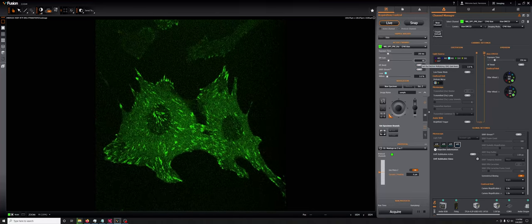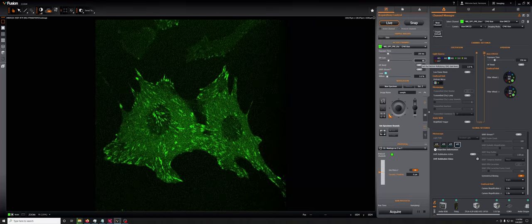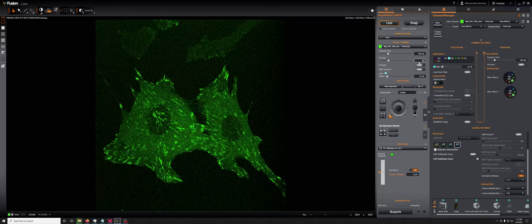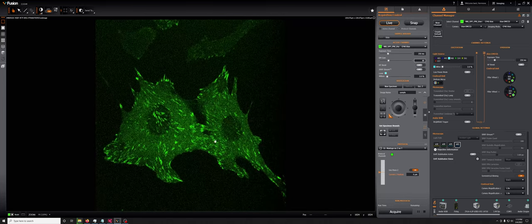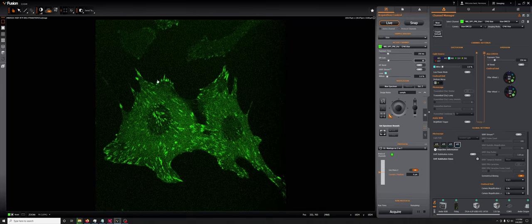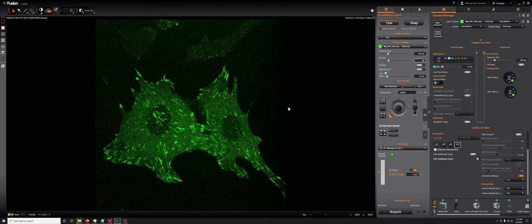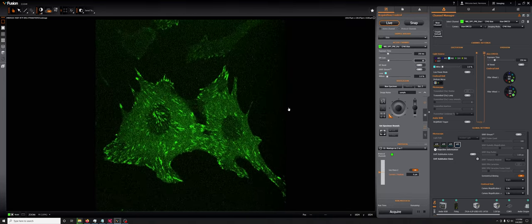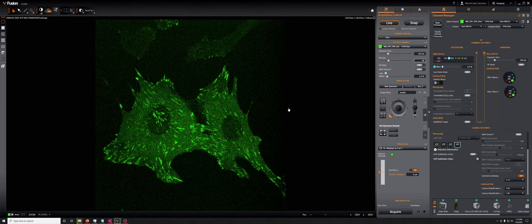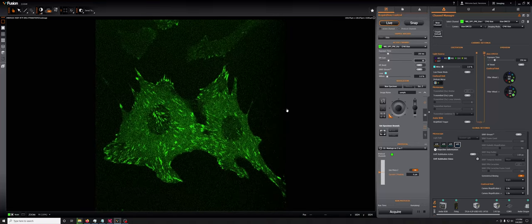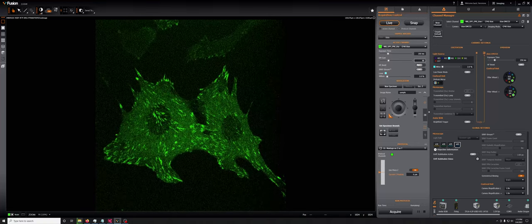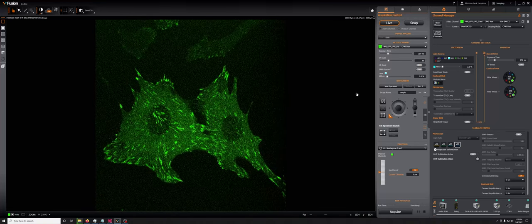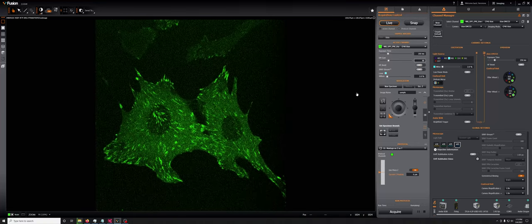So the reason that you don't want to increase the EM gain beyond what you need, based on this sort of contrast evaluation method, is that when you increase the EM gain, you reduce the dynamic range.